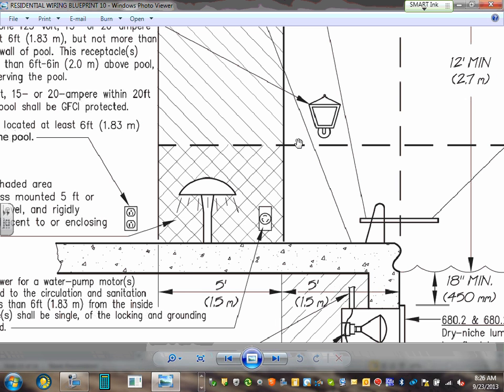Switches are the same for spas and hot tubs, guys. You cannot put a switch closer than 5 feet from the inside wall of a swimming pool, exactly like the spa. Bonding: you are to bond everything metallic with number 8. Anything within 5 feet of the spa or a hot tub must be bonded with number 8 solid copper conductor.